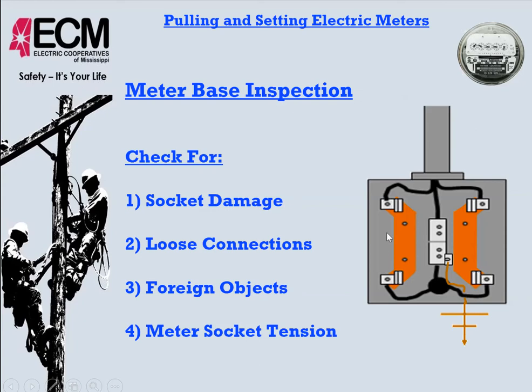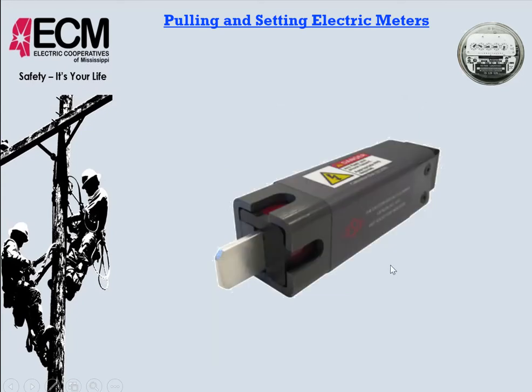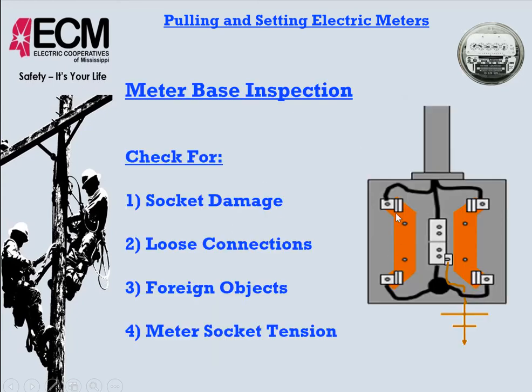Typically on an overhead meter base, again, we don't make the line or the load side up, but it is something we can be aware of. Something you can maybe gently tighten if it were a little loose, but definitely something we'd want to turn down and not be able to safely set the meter, and the homeowner or the property owner could get their electrician back out to tighten those. But just take a look at it: neutral lug, ground lug, line side lugs, and load side lugs. If they appear to be loose, they more than likely are.